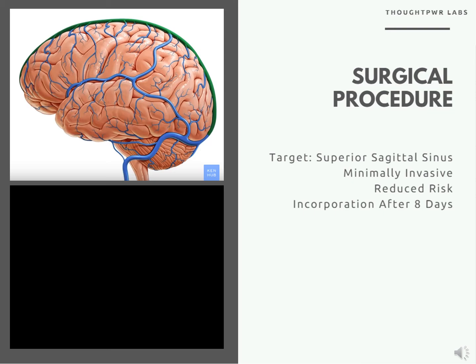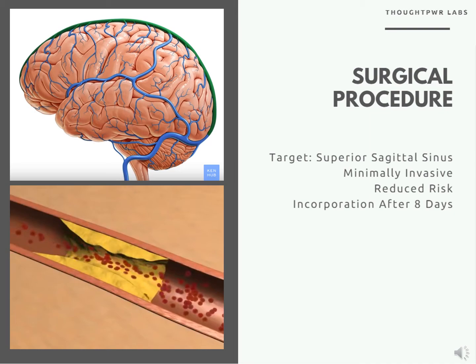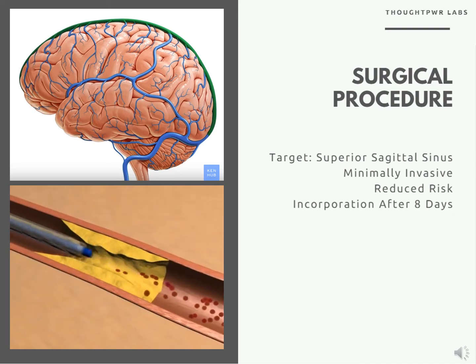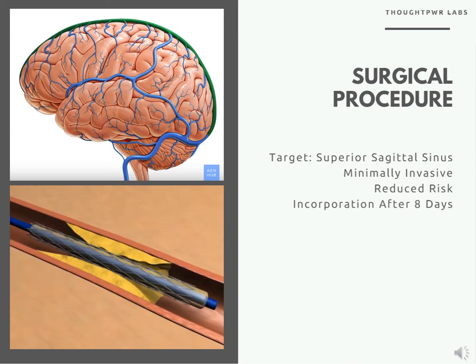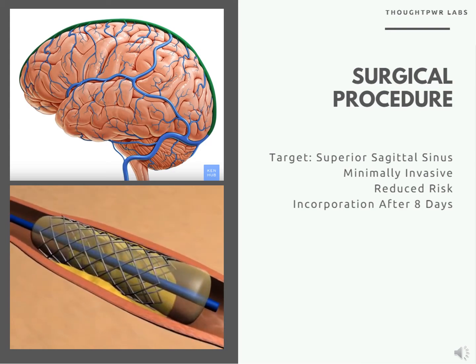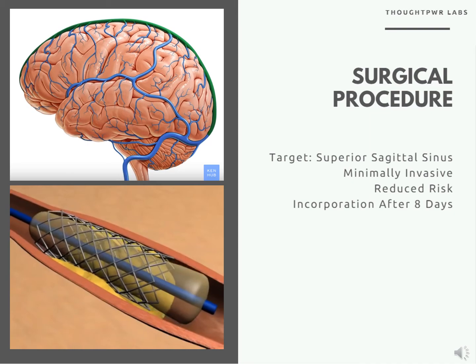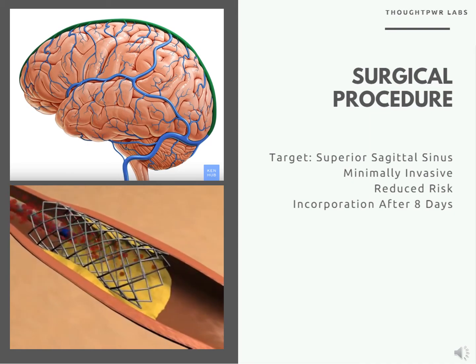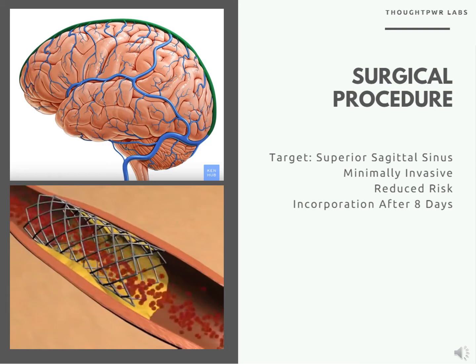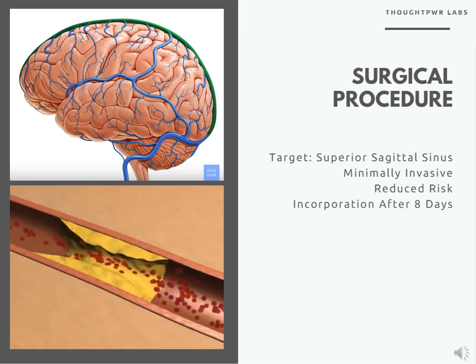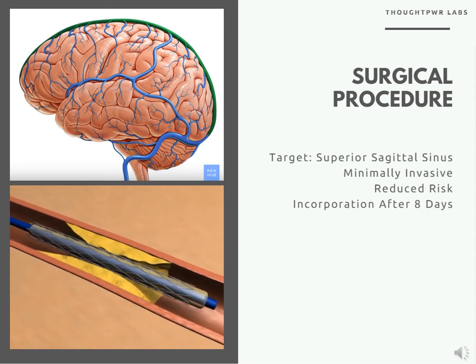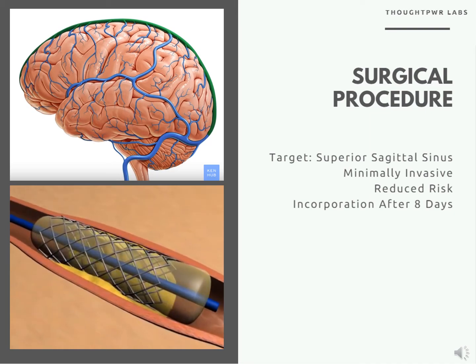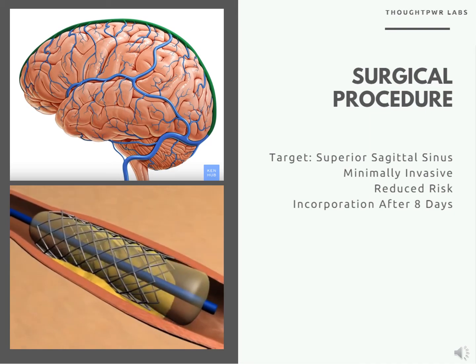The target of the stentrode is the superior sagittal sinus as it runs adjacent to the motor cortex. The surgical procedure to implant this device is minimally invasive and has little risk compared to craniotomies. Mounted over a balloon and implanted via a catheter, it enters the body via a leg or groin artery and is threaded to the correct location. Once arrived, the balloon is inflated to expand the stent. Once positioned, the balloon is removed. Over a period of approximately 8 days, the stent becomes incorporated into the vein, increasing stability, safety, and proximity to the target tissue.